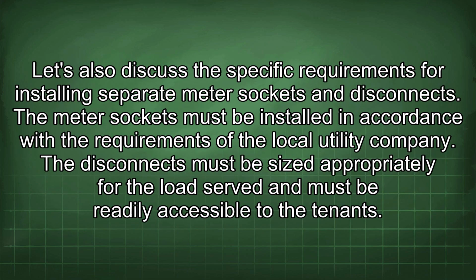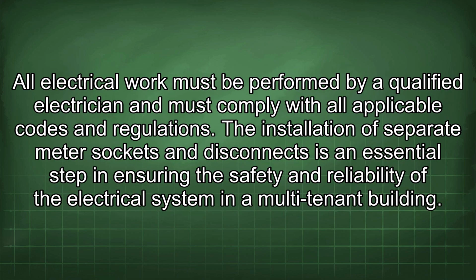Let's also discuss the specific requirements for installing separate meter sockets and disconnects. The meter sockets must be installed in accordance with the requirements of the local utility company. The disconnects must be sized appropriately for the load served and must be readily accessible to the tenant. All electrical work must be performed by a qualified electrician and must comply with all applicable codes and regulations. The installation of separate meter sockets and disconnects is an essential step in ensuring the safety and reliability of the electrical system in a multi-tenant building.